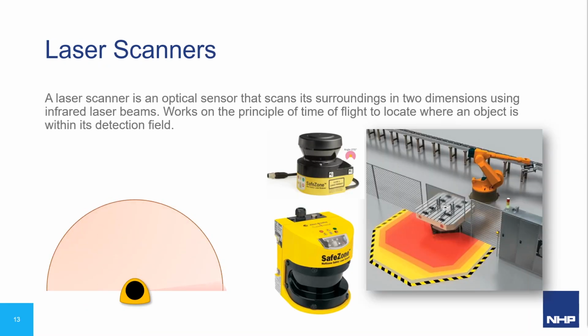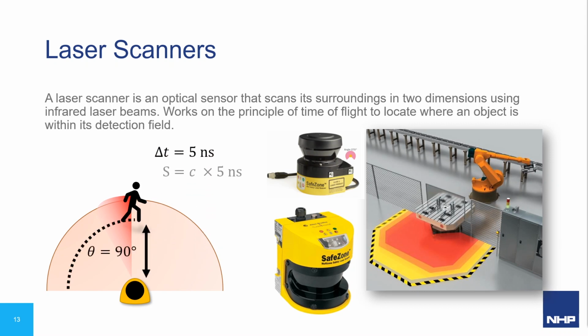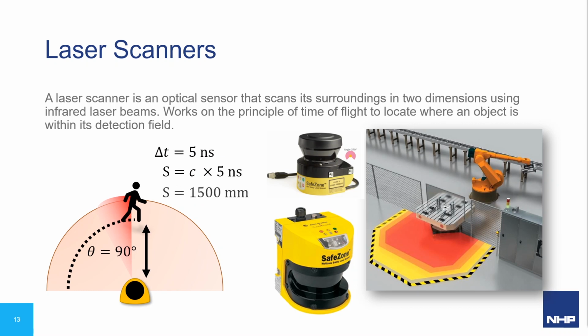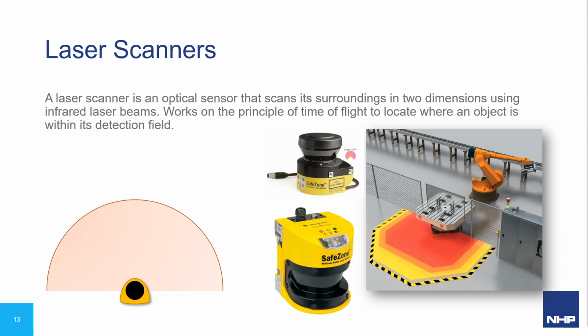Laser scanners are a nicely unique presence sensing device which allows the configurability of a sensing area like safety mats with the non-contact optoelectronic and self-diagnosing capabilities like light curtains. Unlike light curtains which use a transmitter and receiver, a laser scanner is a single device that operates by diffuse laser light. An infrared laser sweeps an area around the scanner and detects objects in its field of view by measuring how much light is reflected back to it. But it can do a lot more with this.